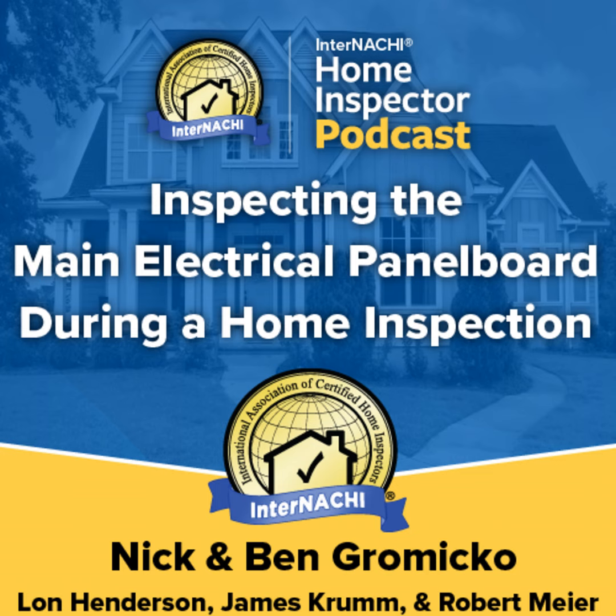The panel board enclosure is designed to keep out foreign objects, protect the conductors and breakers, contain arcing resulting from faults in the enclosure, and protect persons from accidental contact with energized components. Knockouts range in size from 1/2 inch to 2.5 inches in typical residential construction, and are referred to in trade jargon as knockouts simply because a plug has to be knocked out with a tool to create an opening where a box or enclosure has been factory pre-punched. Knockouts being left open and unused in boxes and other cabinets is a very common problem. A knockout opening in a box is sometimes covered with tape, which is not equivalent to the wall of the box, and that is a defect.